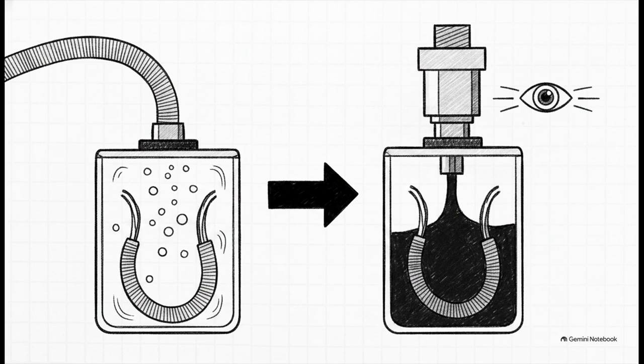I really want to highlight step 2 from that process, vacuum pressure impregnation, or VPI. This is just incredible engineering. Think of this step as literally sucking the air out of the motor's lungs. They drop the pressure all the way down to 10 millibars to completely evacuate every single tiny pocket of air in the wiring. Then they slam it with 6 bars of positive pressure, forcing protective liquid resin into every microscopic crack. The result? There is absolutely zero airspace left for a partial discharge spark to ignite. And just to be completely sure, they verify this solid block of wiring with high-end 3D CT scans.